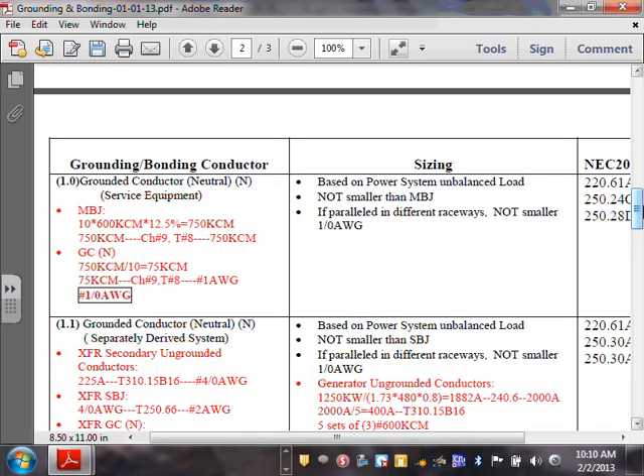Just because you dropped, imagine, all your HVAC equipment. All of them are three-phase, right? They don't carry neutral, almost all of them, right? So HVAC, and that's what, 30% to 45% of your load in any building at any time, is heating, ventilation, and cooling equipment, right? We have light, another 30% of light. The light will be 277, balanced, right? So you balance your loads, and then that will be a neutral load. Receptacles will be a neutral load, but they will be reflected on the primary side as 480, also balanced three-phase. So long story short, I'm not going to convince you. Please raise your hand if you disagree with me. By the time you reach that level, the neutral load is not a whole lot.